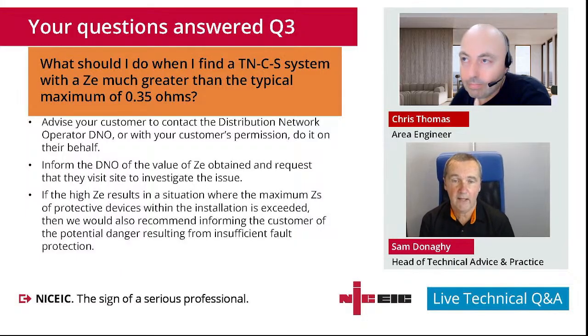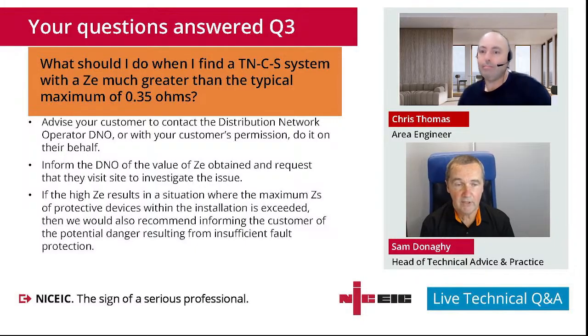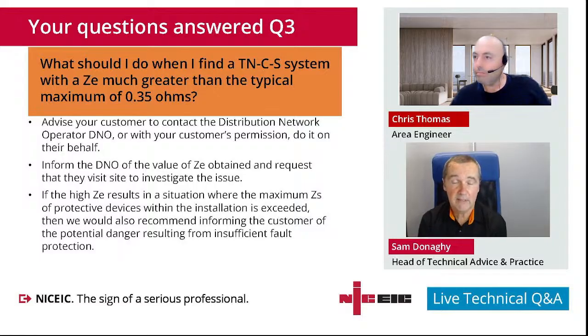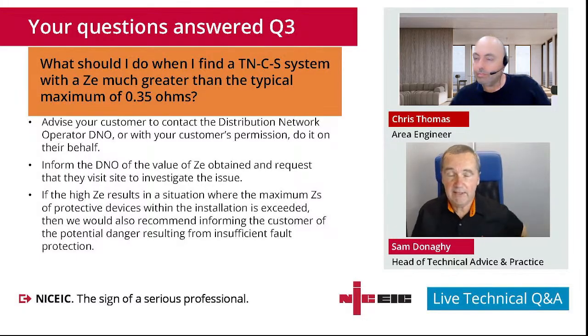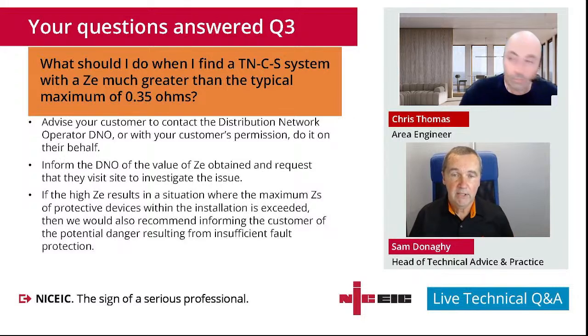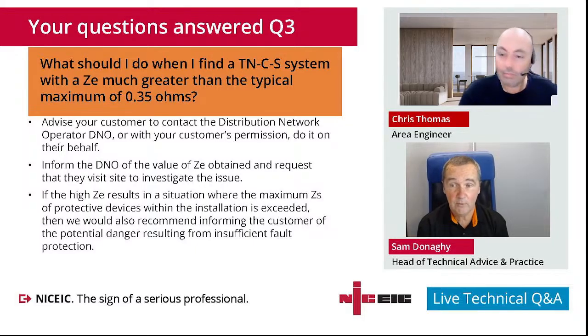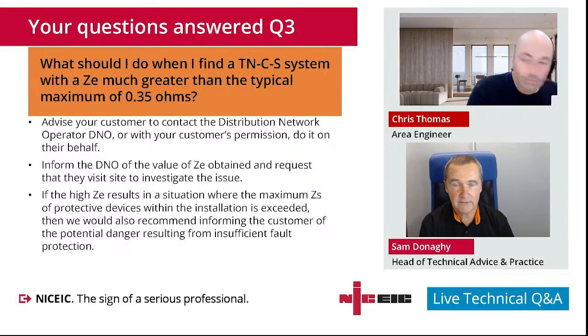If it's slightly over those design thresholds and it doesn't cause you a problem with maximum Zs, then it's just something to record. It is worth notifying the DNO, but it doesn't become an issue. But what you should do is the next time you're at that site to do additions and alterations, or you're doing a periodic inspection, check to see, has it changed again? Has it got worse? In which case there may be information that the DNO would definitely use and would act upon. If it's clearly getting continuously higher, that would indicate that there's a problem in the distribution network that they would look to investigate. Absolutely.